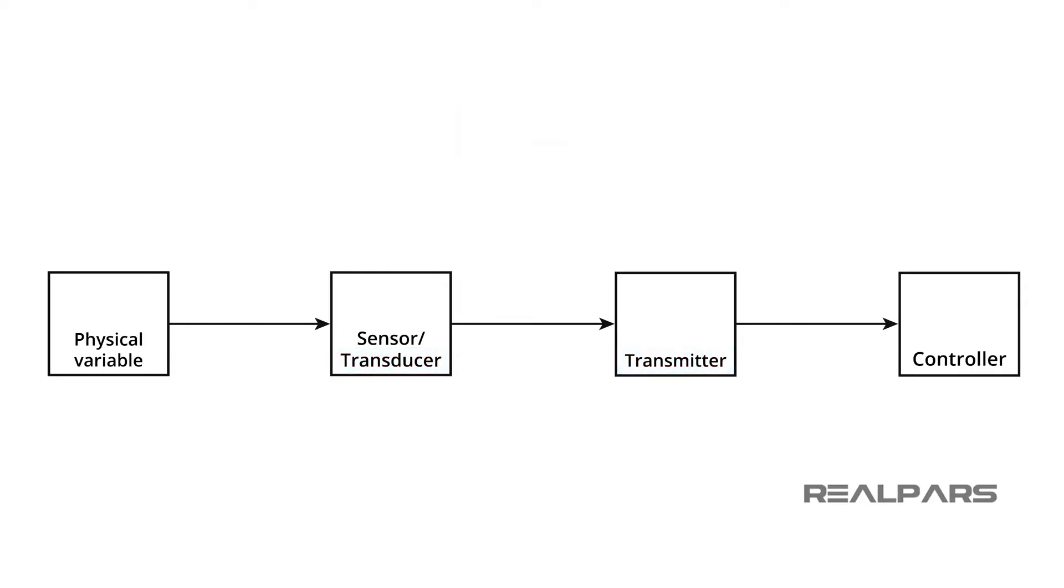As mentioned earlier, the electrical transmitter output signal is usually a range of voltage, 1 to 5 volts, or current, 4 to 20 milliamps. In process control, it is understood that the transmitter output range represents the 0 to 100% of the sensed physical variable. For example, the transmitter would produce an output current range of 4 to 20 milliamps for a measured temperature range of 0 to 150 degrees Fahrenheit.